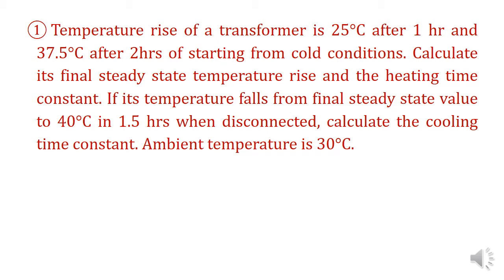Let's consider the first question. The temperature rise of a transformer is 25 degrees Celsius after one hour and 37.5 degrees Celsius after two hours of starting from cold conditions. We need to calculate its final steady state temperature rise and the heating time constant. In the second part, if its temperature falls from the final steady state value to 40 degrees Celsius in 1.5 hours when disconnected, we must calculate the cooling time constant. Ambient temperature is given as 30 degrees Celsius. We consider both heating and cooling cases.